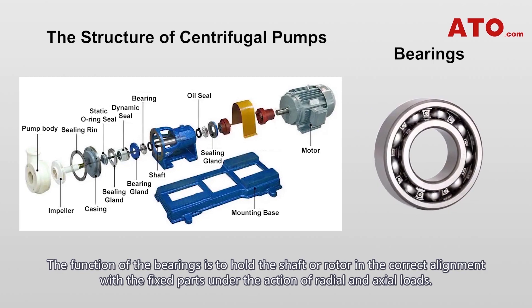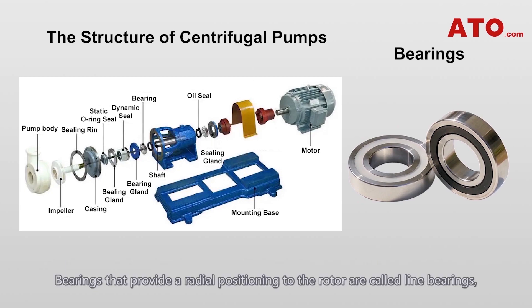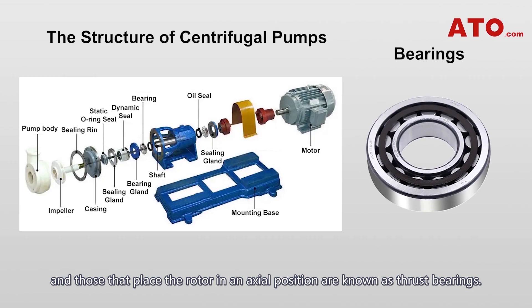The function of the bearings is to hold the shaft or rotor in the correct alignment with the fixed part under the action of radial and axial loads. Bearings that provide a radial positioning to the rotor are called line bearings, and those that place the rotor in an axial position are known as thrust bearings.